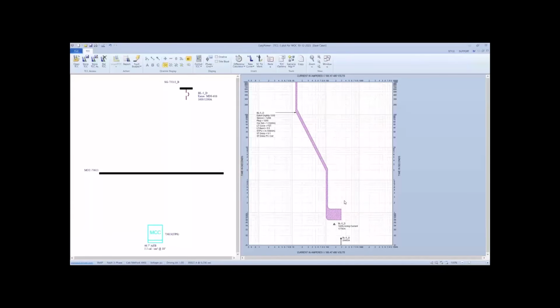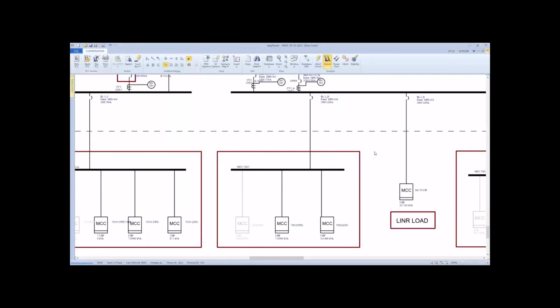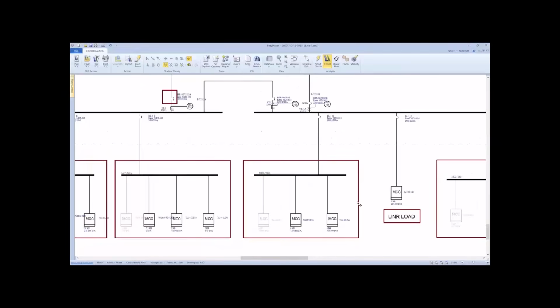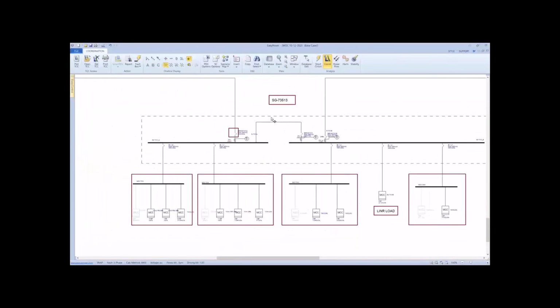From my point of view, the 2-second setting doesn't affect coordination, right? It obscures it. It's allowed by the standard to limit the max time for arc flash calculation, but if you do it prematurely, you obscure exactly the conflict you find with the arcing current.